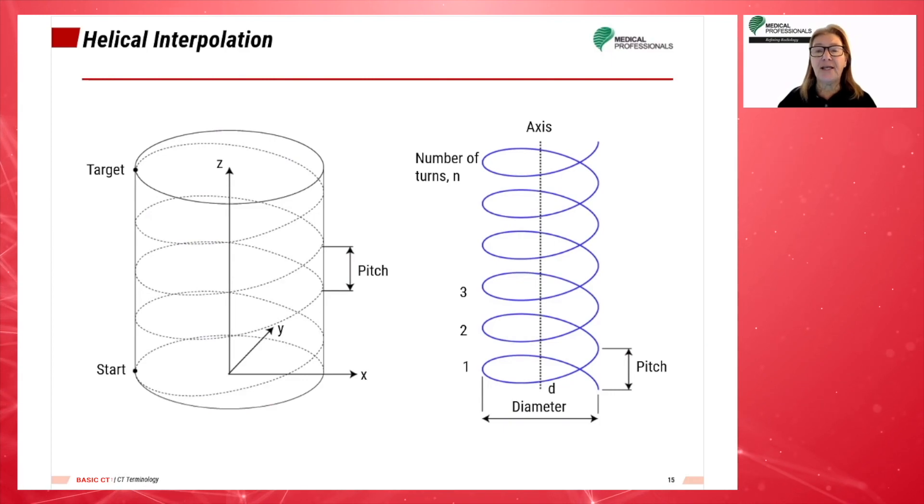Interpolation is a mathematical process used to smooth, enlarge, or average images that are being displayed with more pixels than that for which they were originally reconstructed. Since helical scanning occurs in a pattern that is at an angle to the perpendicular desired, interpolation is used to straighten up the section. This can be done through algorithms creating sections that are reconstruction of data and not additional radiation to the patient.